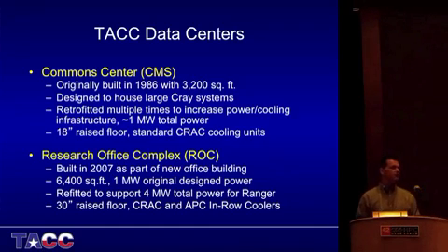So to give you an idea of the two data centers: we have a challenge in that we had a really old data center built in 1986, originally designed to house Cray big iron systems. It's been retrofitted multiple times, the same story you probably hear at many old data centers. We've had to retrofit it with both power and cooling infrastructure, and now we've maxed out what we can provide in the room. We have a total of about 1 megawatt of total power in the room, but we're out of chill water, we cannot supply any more chill water into the room. In fact, our campus, where we're located on the research campus in Austin, is completely out of chill water. They're actually working on building new big chilling towers. It's an 18-inch raised floor with just standard CRAC cooling in that room.